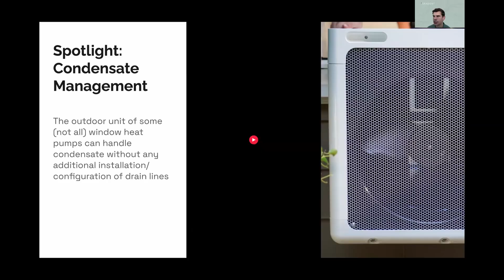Another really interesting thing that happens with window heat pumps, the most common architecture is this saddle architecture that I'm showing here. You can look at the heat exchanger here and the breathing area of this system, and it's big. This is a larger heat exchanger and more cross-sectional area to breathe than nearly all window ACs, and most PTACs and mini splits. What you get with that big breathing area is higher airflow, which means more efficiency. Some of these systems have a dual outlet design, which means you can point air up or down.